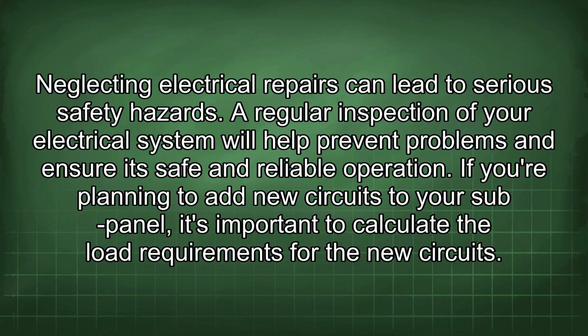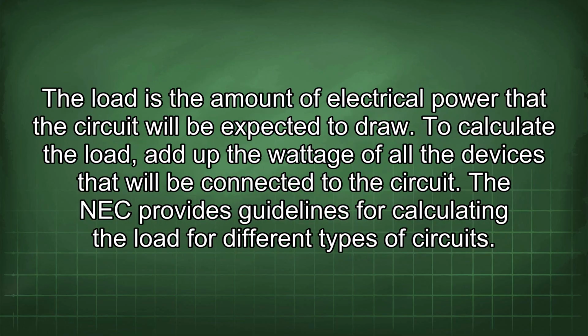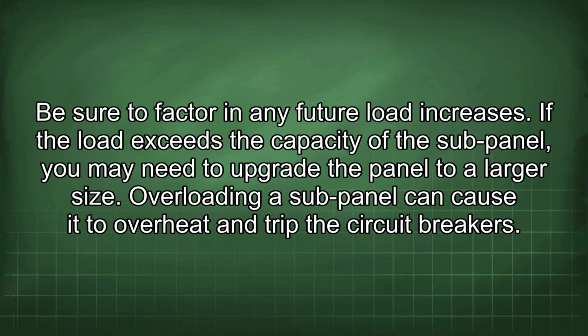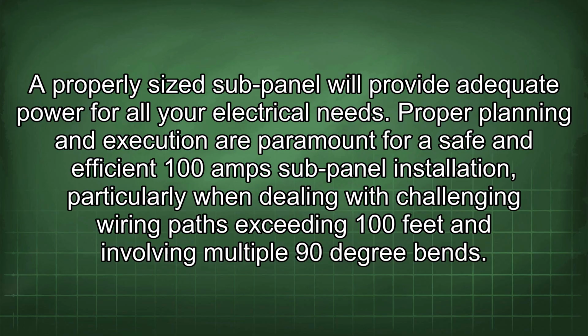If you're planning to add new circuits to your sub-panel, it's important to calculate the load requirements for the new circuits. The load is the amount of electrical power that the circuit will be expected to draw. To calculate the load, add up the wattage of all the devices that will be connected to the circuit. The NEC provides guidelines for calculating the load for different types of circuits. Be sure to factor in any future load increases. If the load exceeds the capacity of the sub-panel, you may need to upgrade the panel to a larger size. Overloading a sub-panel can cause it to overheat and trip the circuit breakers. A properly sized sub-panel will provide adequate power for all your electrical needs.